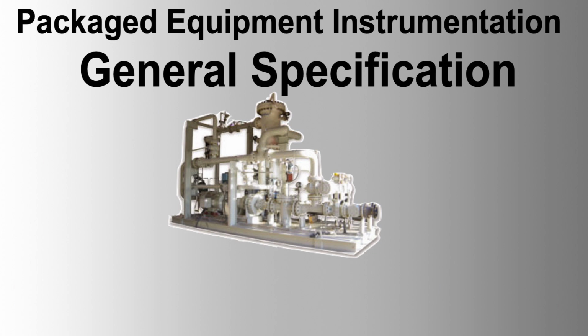Instrument cables and ancillaries. General: stranded copper conductor cables are preferred. Underground cables should be XLPE or PVC or EPR insulated, lead sheathed, single galvanized steel wire armored, and PVC oversheathed. Segregation of signal cables: intrinsically safe signals should use multi-core cables with distinct color coding and appropriate segregation from non-IS circuits. Instrument cable glands should be metric thread metallic brass with nickel plating, dual certified to Ex d and Ex e, and weatherproof to IP66.